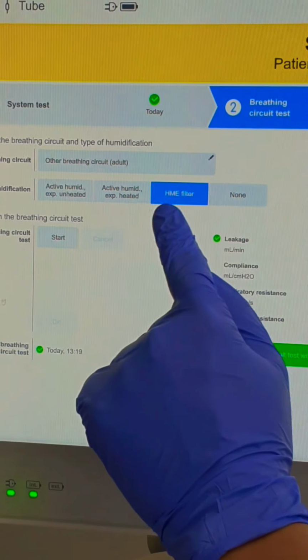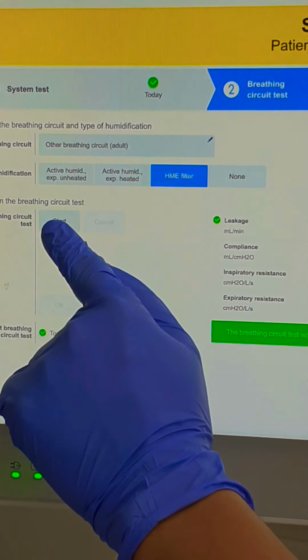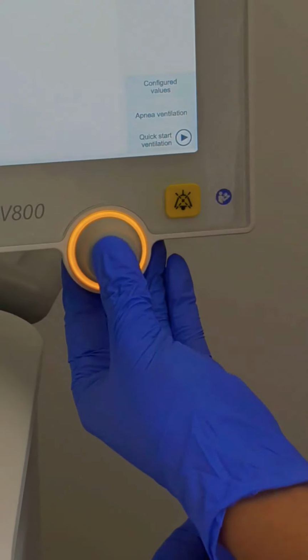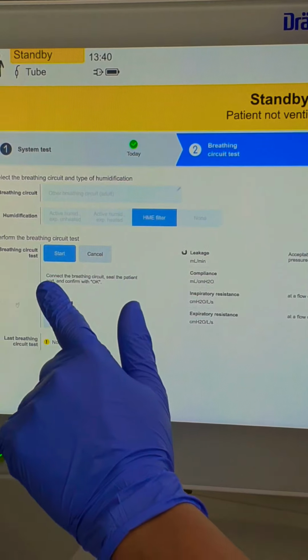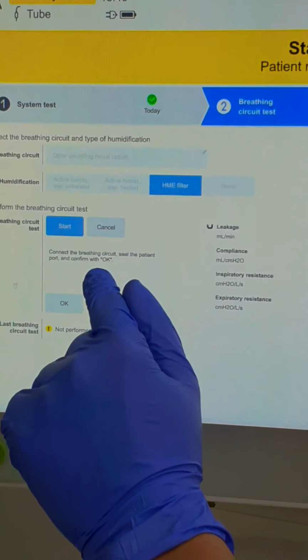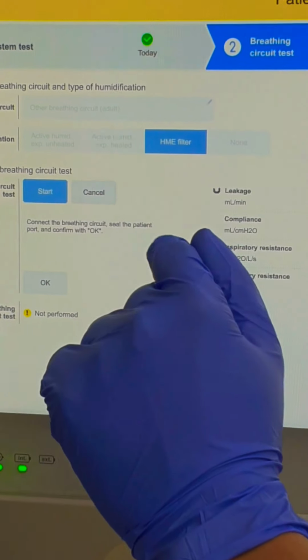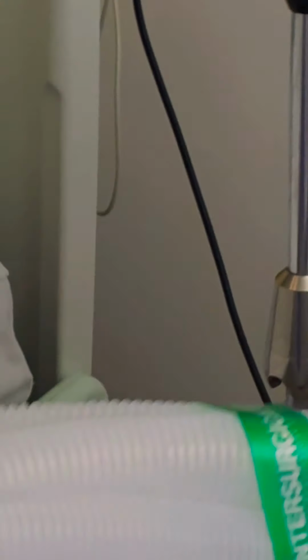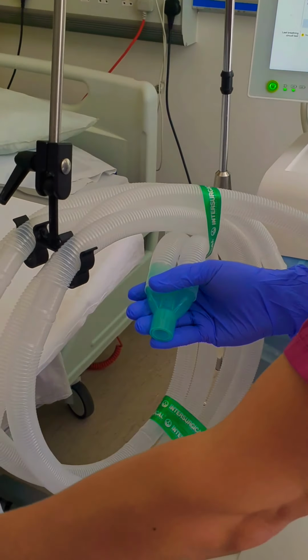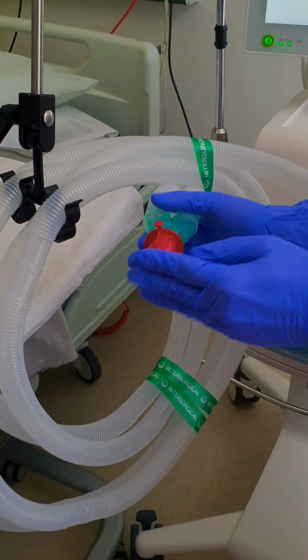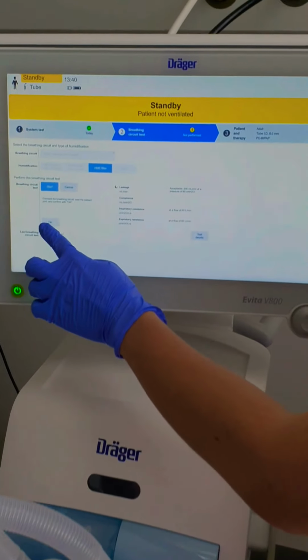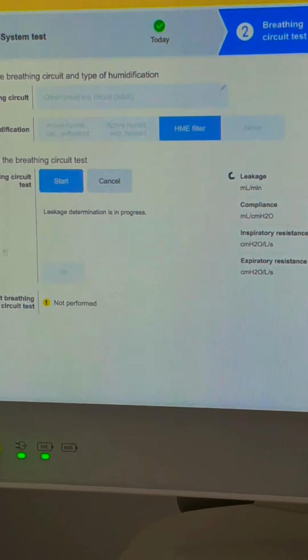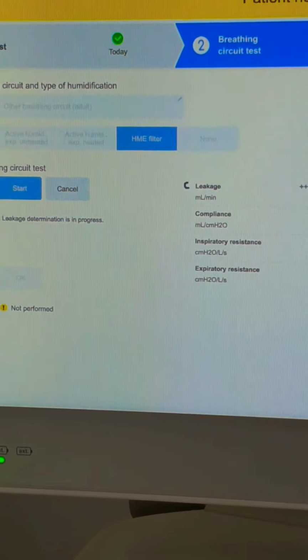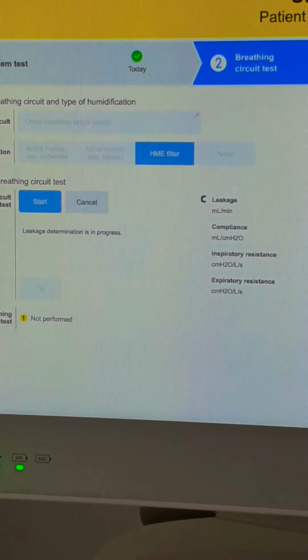If you notice here, we're going to be using the HME filter, and we're just going to press start, and then again press the rotary knob. If you go back to this corner here, it says connect the breathing circuit, seal the patient port, and confirm with OK. That means we have to remove the test lung and then cap it off with the red cap, and we press OK on the screen, and it should proceed to testing the circuit for leakage, compliance, inspiratory resistance, and expiratory resistance.